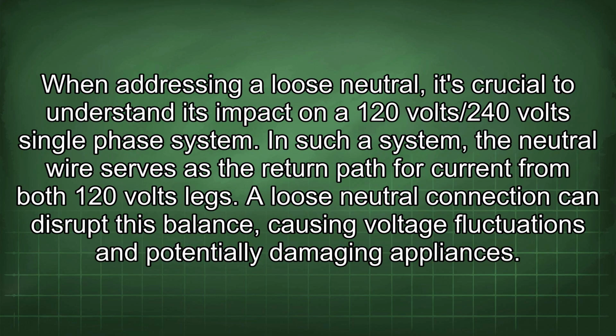When addressing a loose neutral, it's crucial to understand its impact on a 120 volt/240 volt single-phase system. In such a system, the neutral wire serves as the return path for current from both 120 volt legs. A loose neutral connection can disrupt this balance, causing voltage fluctuations and potentially damaging appliances.